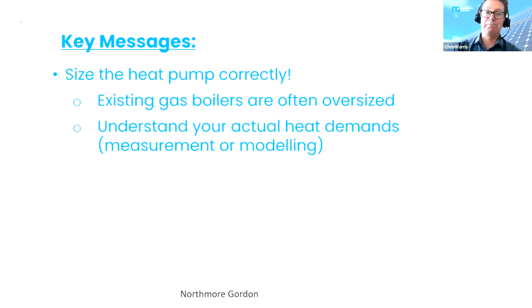So my key messages, and the key messages that everyone has said, is really key to size that heat pump correctly. The existing boilers are often oversized, and you need to understand your actual heat demands, either by measuring your actual heat demand, or modeling it using a good model. And this is particularly important because it's not just the pool heating. You've got pool heating, you've got air heating, and you've got domestic hot water heating for your showers, and they all need to be sized correctly.